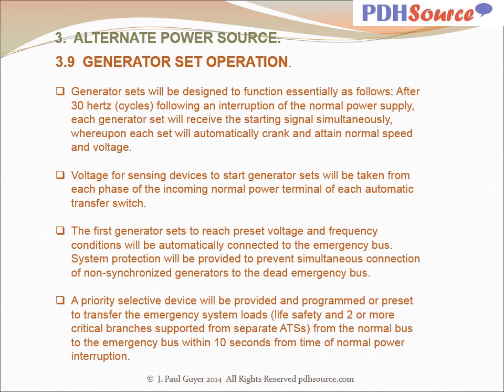Generator sets will be designed to function essentially as follows. After 30 cycles following an interruption of the normal power supply, each generator set will receive the starting signal simultaneously, whereupon each set will automatically crank and attain normal speed and voltage. Voltage for sensing devices to start generator sets will be taken from each phase of the incoming normal power terminal of each automatic transfer switch. The first generator sets to reach preset voltage and frequency conditions will be automatically connected to the emergency bus. System protection will be provided to prevent simultaneous connection of non-synchronized generators to the dead emergency bus.